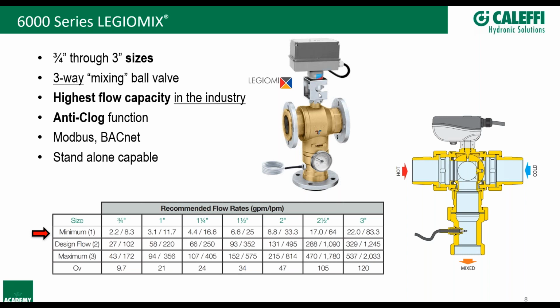About the only thing I would say with installation is that you don't want the actuator upside down. You don't want it on the bottom side of the valve. It's not hermetically sealed, so if you do get water going up through the stem or off of a joint somewhere, you could actually cause issues with the actuator. But really, as long as it's kept at the 9 o'clock, 3 o'clock, or 12 o'clock positions, you're going to be in good shape.